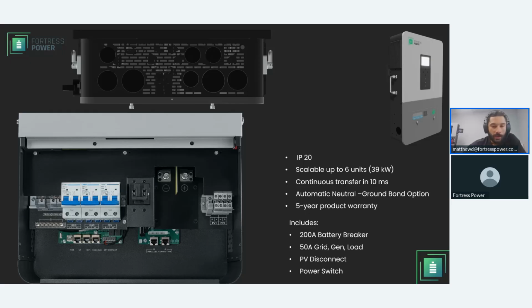Okay. So as I mentioned before, it is an indoor inverter, IP20, scalable to 6 units with a transfer switch of 10 milliseconds, which is pretty impressive, pretty seamless. It has an automatic neutral ground bond. So what that means is, usually when you do a ground bond, you would do it at the meter or at the main panel, basically where the grid feeds in. But if you were to do this in an off-grid situation, potentially where the grid is not accessible, then the inverter has the capability of bonding at the source, which in this case would be the inverter. And that would just be on the LCD parameter settings, which we'll go over very soon.